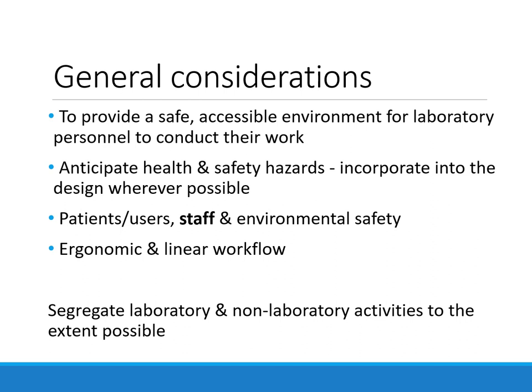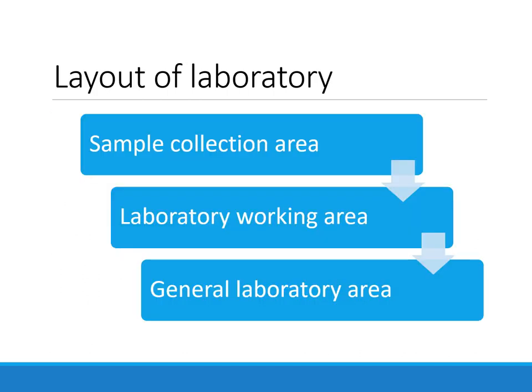General considerations to be kept in mind while designing a laboratory: to provide a safe, accessible environment for laboratory personnel to conduct their work; to anticipate health and safety hazards and incorporate corrective measures into the design wherever possible. The safety of the patients or users, the staff, and the environment must be taken care of. There must be an ergonomic and linear workflow in the lab — ergonomic means designed for efficiency and comfort in the working environment. Additionally, the laboratory and non-laboratory activities must be segregated as much as possible.